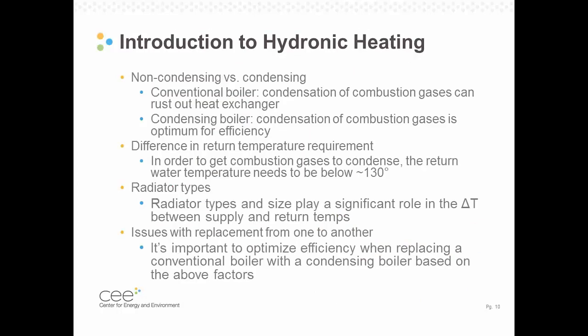A couple things to note is that it's important to understand the difference between a non-condensing or a conventional boiler versus a condensing or more high-efficiency boiler. The key aspect is whether you want those gases to condense or not. In a conventional boiler, if the gases condense, then you could potentially have some failure issues on the heat exchanger. The heat exchanger isn't built out of materials that can withstand rust, so we really are trying to prevent condensing happening in that system. On the flip side, a condensing boiler is meant to condense, so those heat exchangers are made out of durable materials that can withstand the corrosive qualities of condensate. And in order to get the efficiency of a condensing boiler, we want that to condense as much as possible.